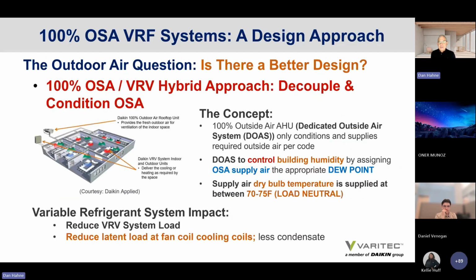So a 100% outside air system that is decoupled from the variable refrigerant system is a good way to downsize the actual variable refrigerant component serving the occupied classification, the high probability classifications of standard 15. The concept is that you decouple the 100% outside air, you let the DOAS unit control building humidity by using a lower dew point on the coil temperature and to actually provide effective control of the space.